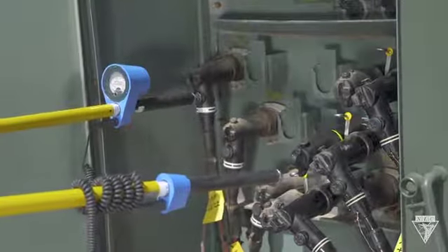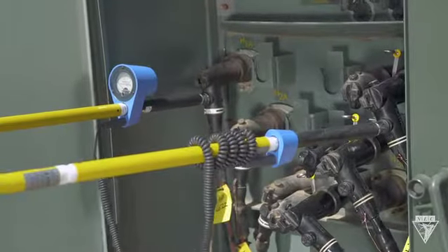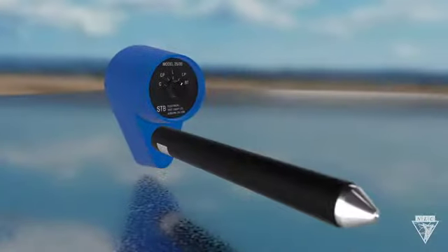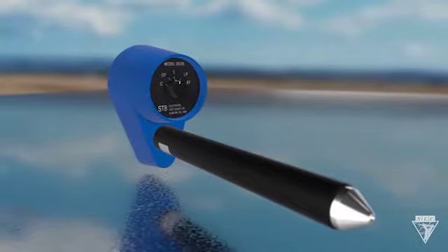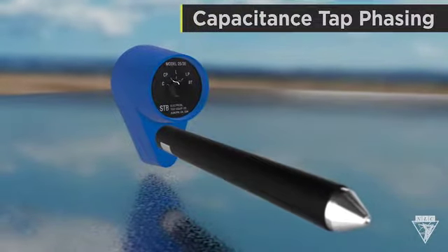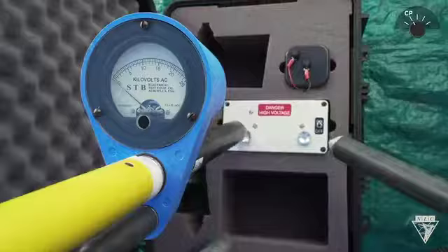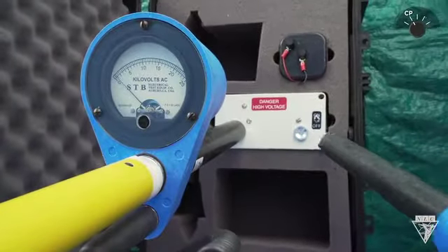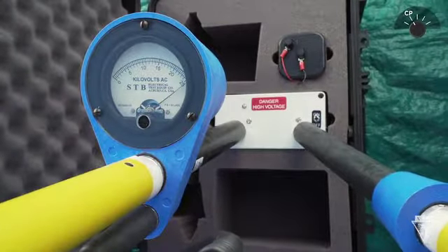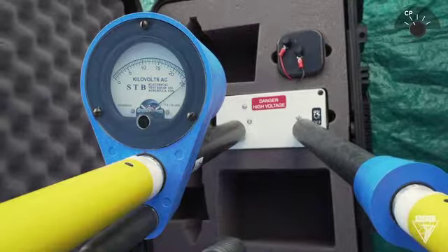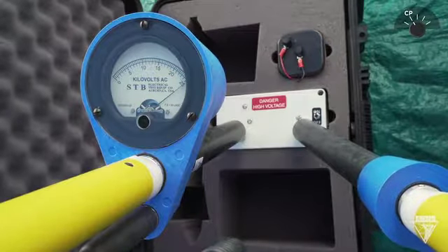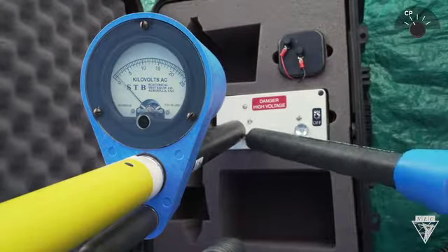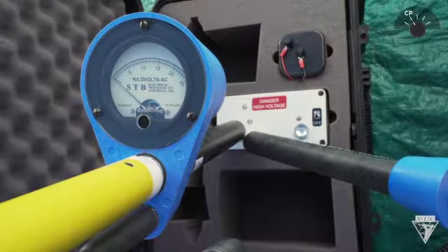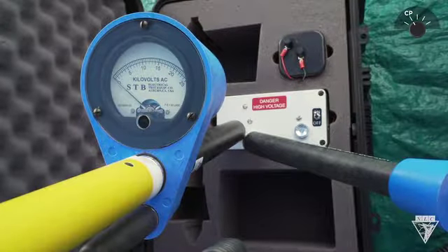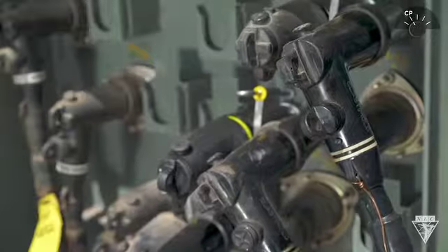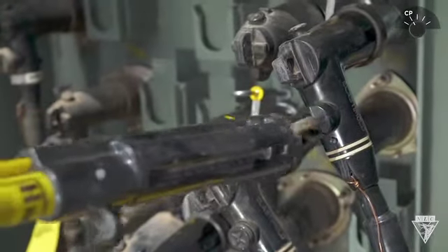Some companies utilize capacitance test points for underground conductors. For this kind of test, turn the phasing voltmeter dial to CP, capacitance tap phasing. Perform the same proof test as before, but recognize a couple differences on CP mode. Needle deflection should be greater than full. When you touch the probes together on the raised washer, needle deflection should read less than 5 kV. After testing, the meter can now be used to check phasing on primary underground lines at capacitance test points.